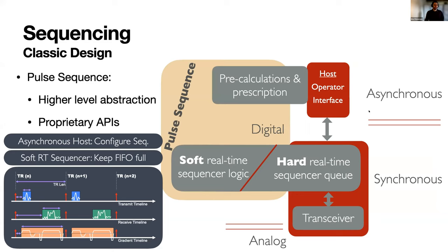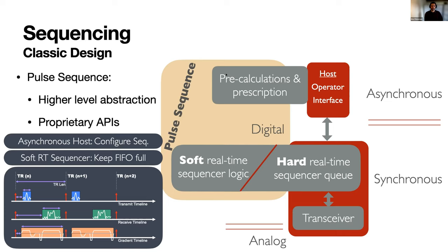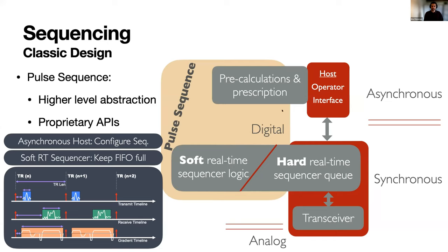Getting into the sequencing a little bit more, this is sort of a typical pulse sequence. It spans an asynchronous and synchronous side of the MRI system. Typically there's some pre-calculations and prescriptions that happen which is then sent to the real sequencer logic, which then interprets that and keeps this queue—keeps the scan queue full, so it keeps the waveform queue appropriate for the scan that's happening. That's how the standard system works. You get the data to come back and this is proprietary and usually relatively high level.